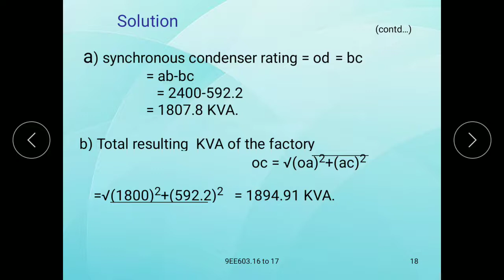From the above problem, we can conclude that the KVA required by the factory has reduced from 3000 KVA to 1894.91 KVA, at the expense of a synchronous condenser of 1807.8 KVA. Improved power factor will give a good amount of savings in the energy bills.